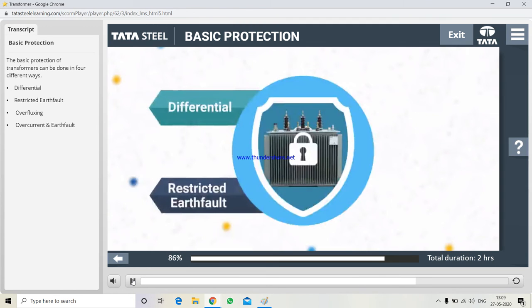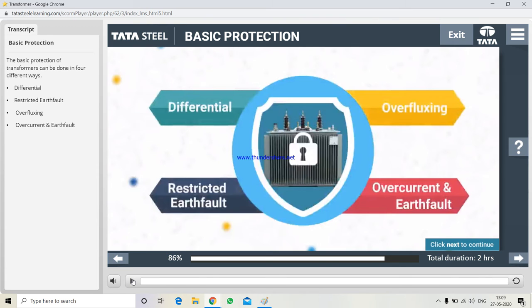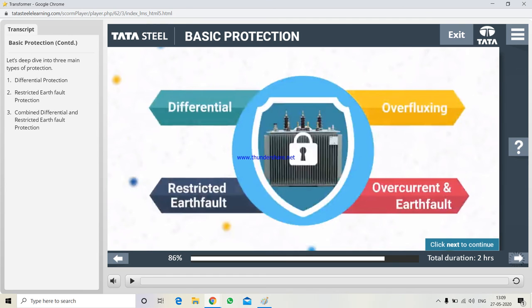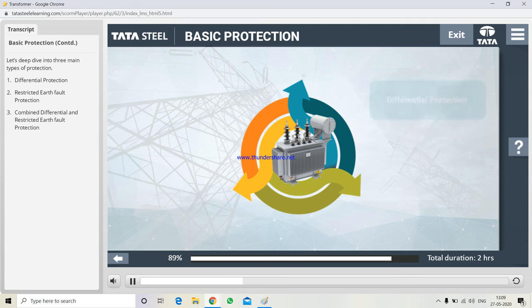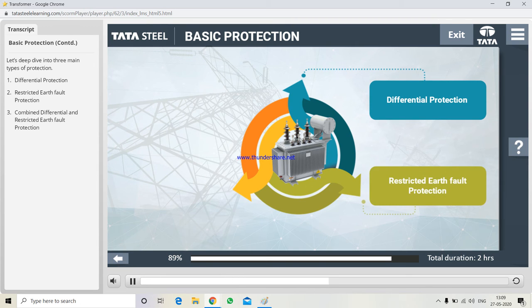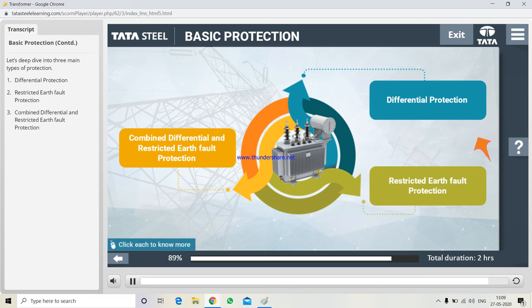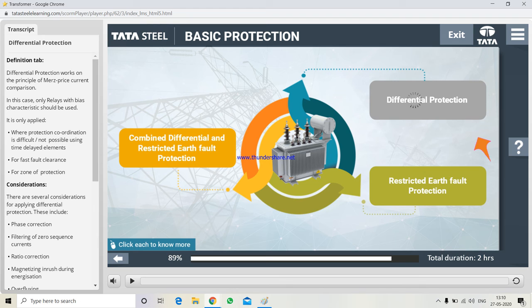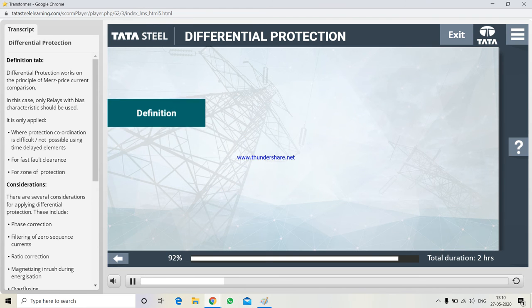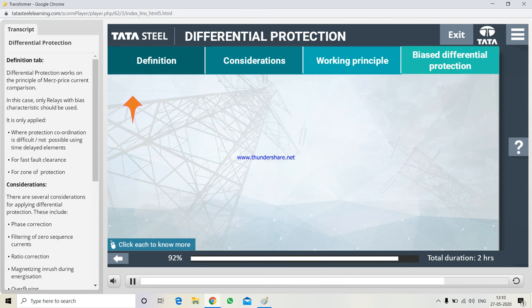Can be done in 4 different ways: differential, restricted earth fault, overfluxing, overcurrent and earth fault. Let's deep dive into 3 main types of protection: differential protection, restricted earth fault protection, combined differential and restricted earth fault protection. Click each to know more.